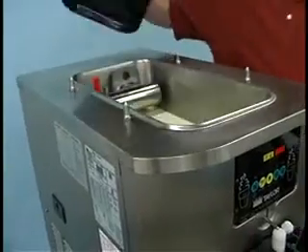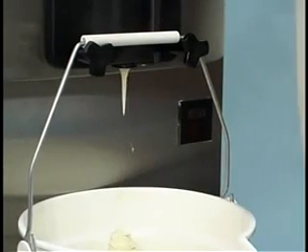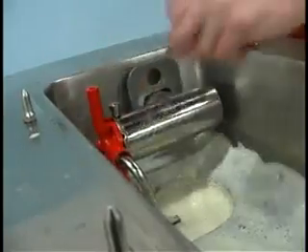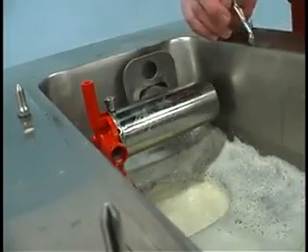Remove the hopper cover and take it to the sink for cleaning. When the flow of product stops, press the wash and pump keys and close the draw valve. Remove the assembled air mix pump and take it to the sink for further disassembly and cleaning.